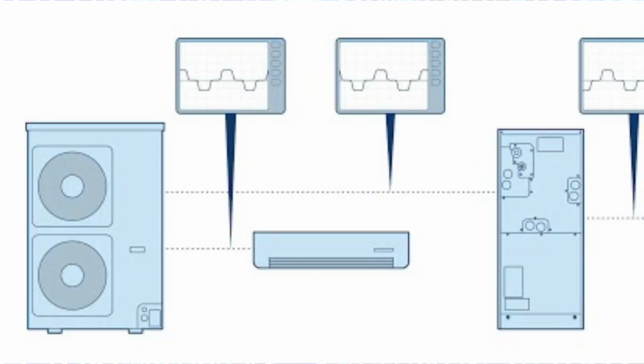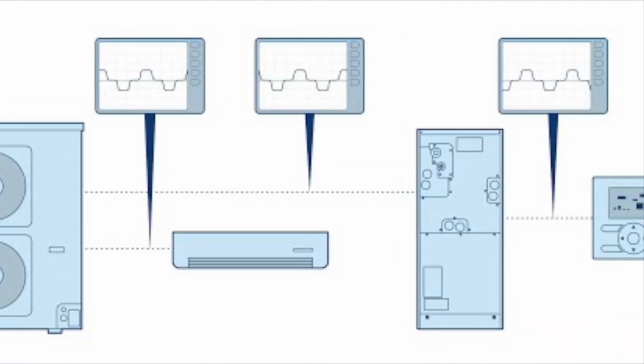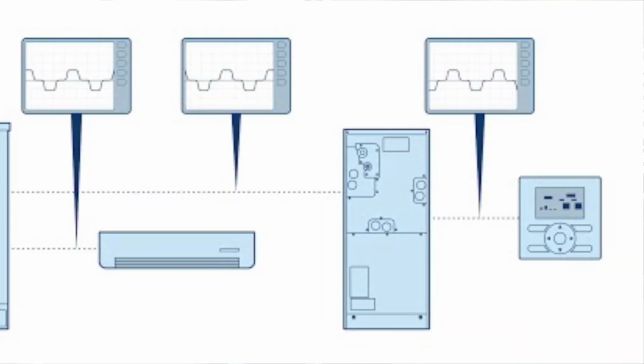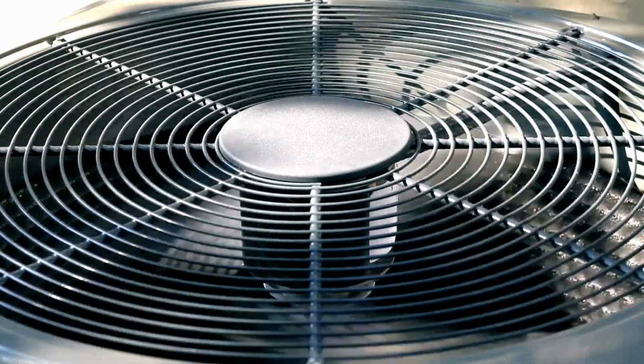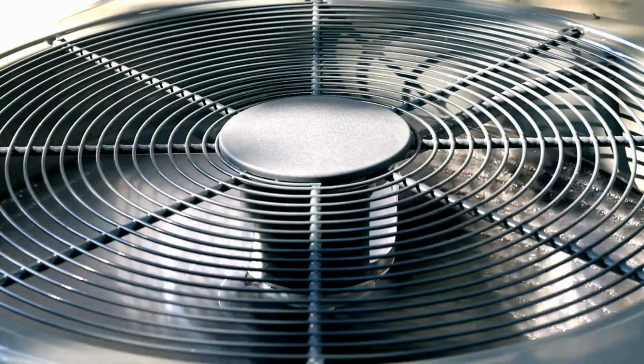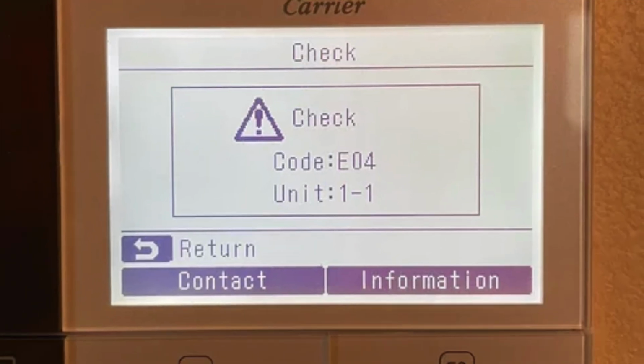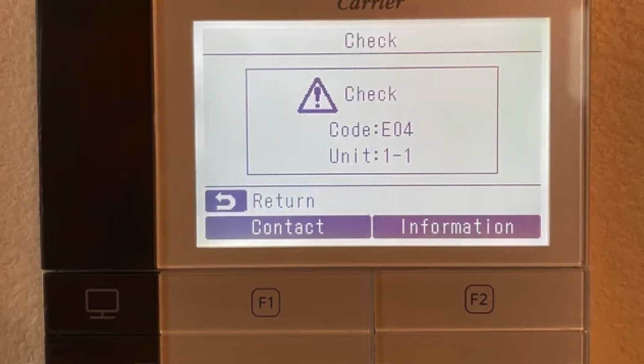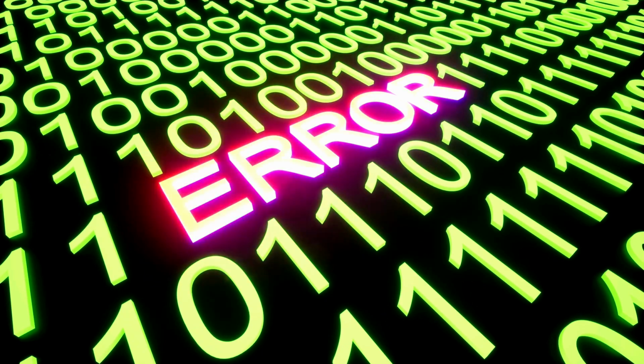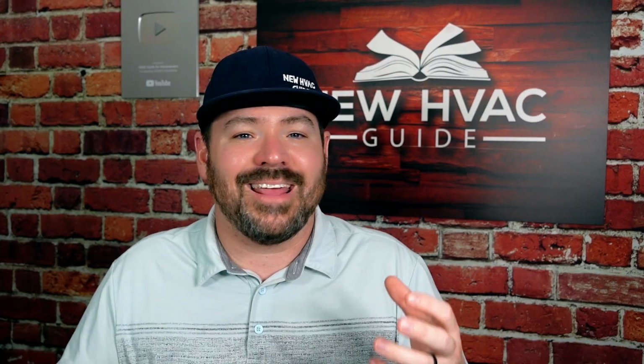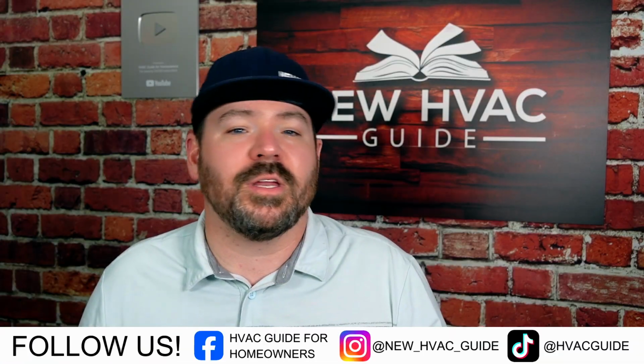If you hear someone say communicating, that system really, in a lot of cases, only needs two wires. It's going to send data back and forth on those wires. It's very similar to the internet, and the equipment has more capabilities because of that. The outdoor unit might be able to say, hey, it's not that hot out today, let's just barely run, let's run at a much lower speed. It has other capabilities, like if something goes wrong, it can send that data to the controller or the indoor unit and say, hey, I'm seeing something wrong here, send an error code of some type.